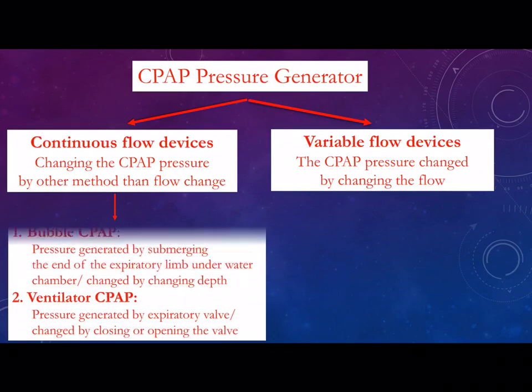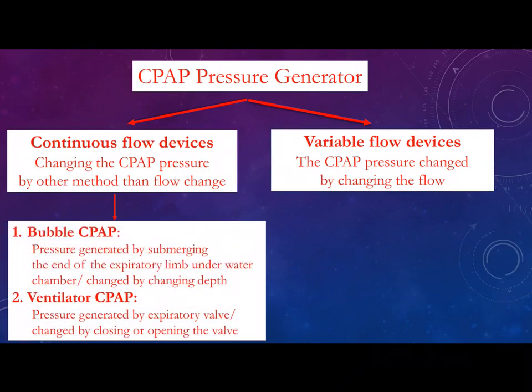An example of continuous flow CPAP is the famous bubble CPAP, where pressure is delivered by submerging the end of the expiratory limb under the water chamber. The pressure is changed by changing the depth of the end of the expiratory limb — increasing the depth increases the pressure. Another example is the ventilator CPAP, where the expiratory limb is connected to the ventilator and we increase or decrease the CPAP pressure using the PEEP valve.